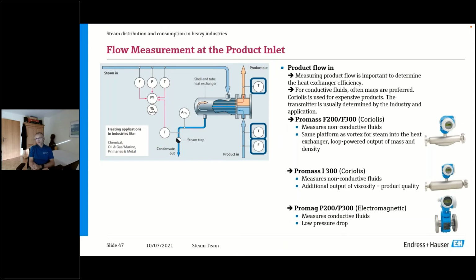On the product side, this is classical Endress+Hauser business, of course. When it comes to oils, hydrocarbons that you're heating, then you would use a Coriolis meter, like our Promass F or even better, the Promass Q. That is a very nice, relatively new device, or the Promass I, that not only provides you measuring of mass and density, but also the viscosity. And for conductive fluids, of course, you would want to choose a mag meter like the Promag P200 or P300.